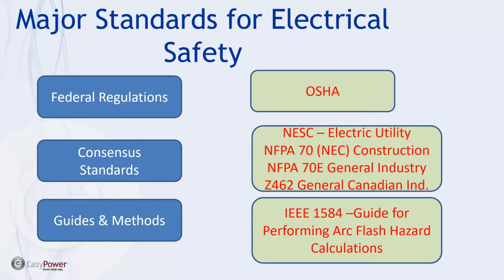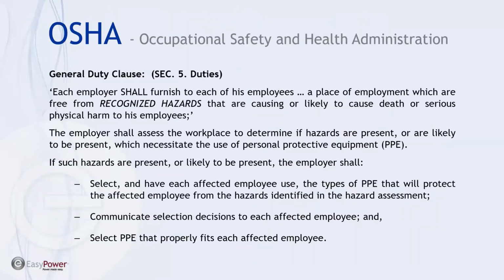Most of these don't just dictate specifically what guides or methods should be used for calculating arc flash, but what we focus on is regarded as the national standard recognized internationally, IEEE 1584, because it's based on test data that was generated by IEEE and industry partners.